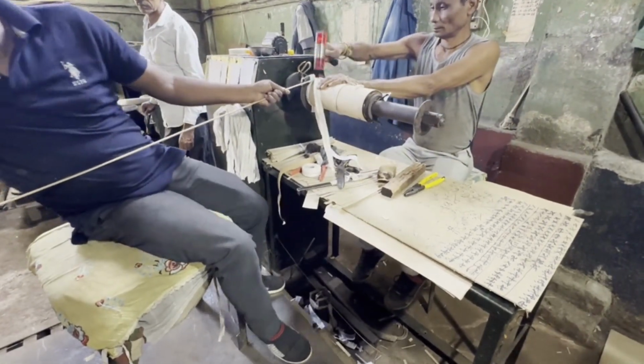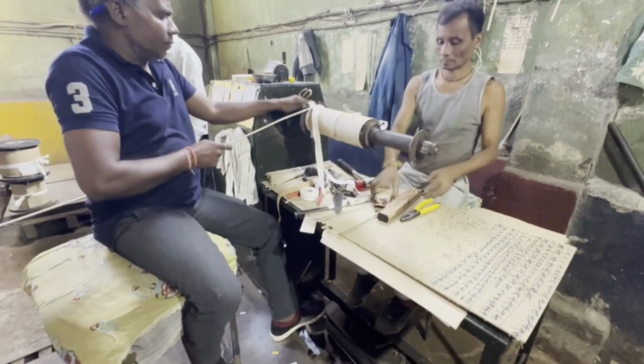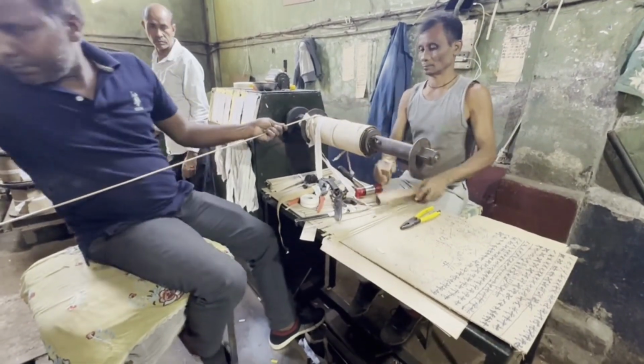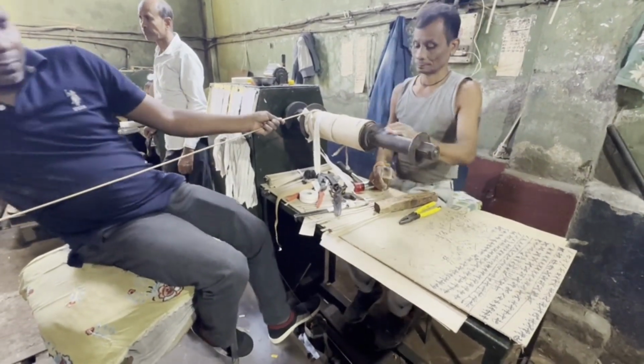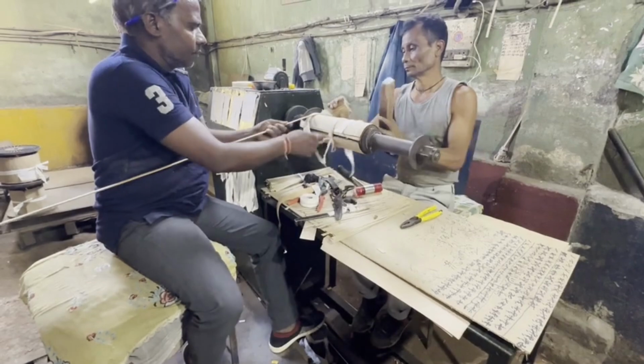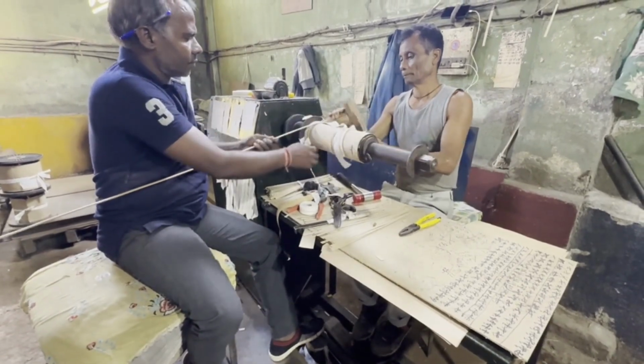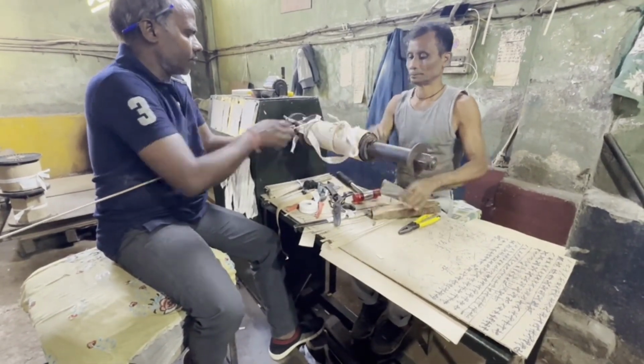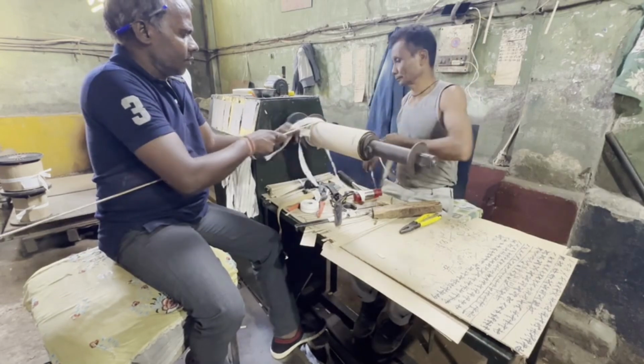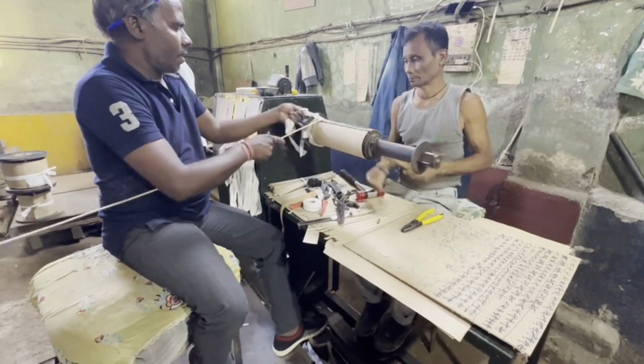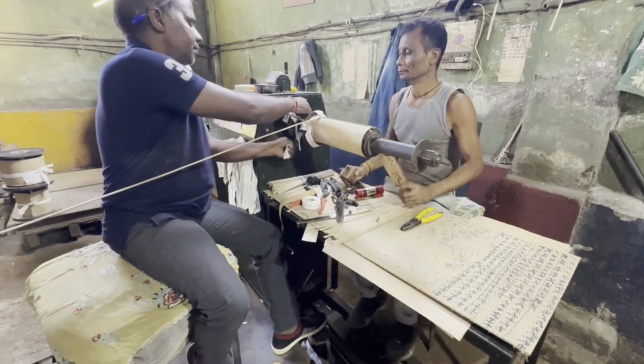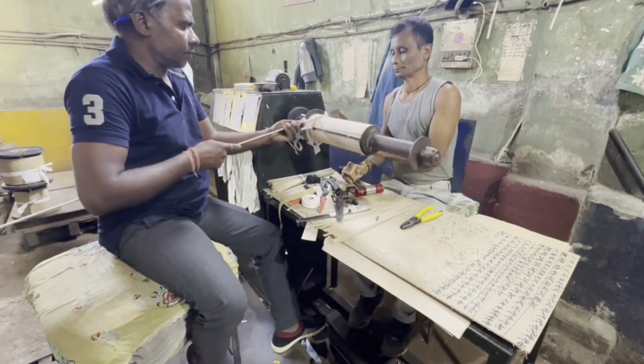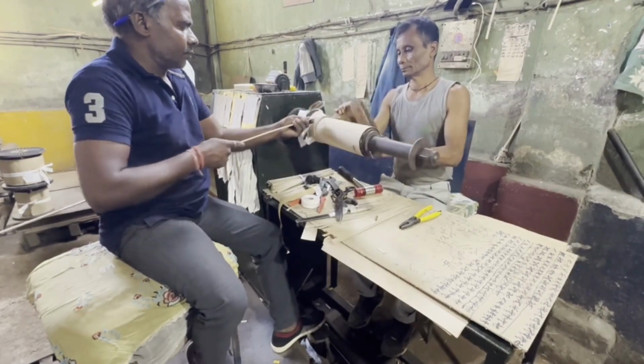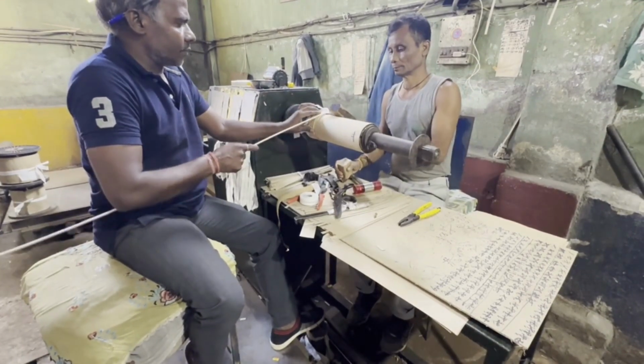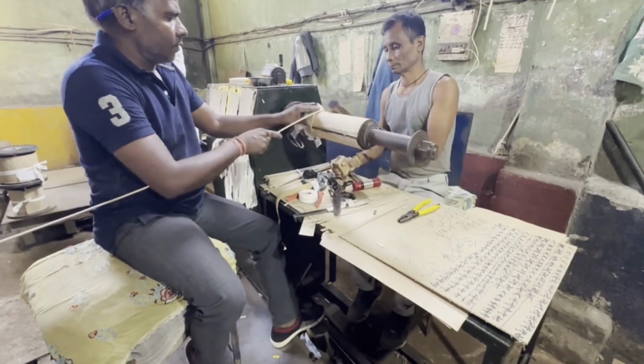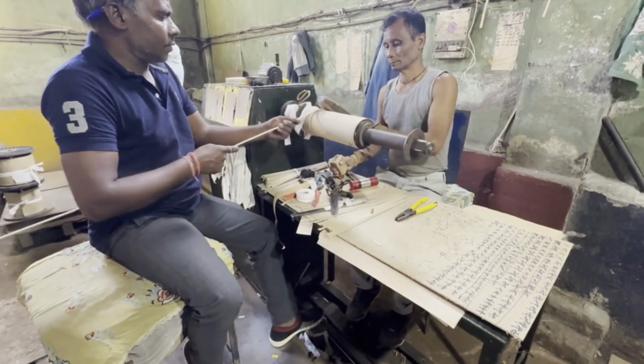The paper insulation you see here doesn't just separate turns. After oil impregnation, it becomes part of the transformer's dielectric system, increasing insulation strength. Now imagine a short circuit on the secondary side. Fault current rises instantly. Huge mechanical forces try to push these windings apart. If the winding pressure is weak, displacement happens. And once windings shift, internal faults are almost inevitable.